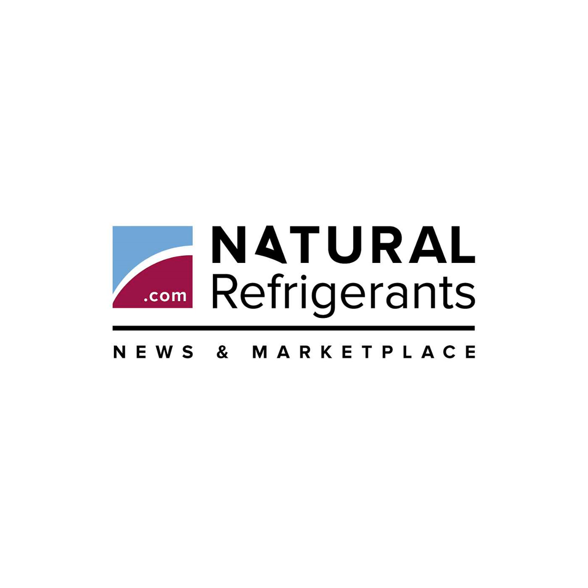It formed a working group on A3 and A2L mildly flammable refrigerants, to consider proposals to enable safe use of R290 and other near-zero emissions next-generation refrigerants. ASHRAE has also started an effort to increase the allowable charge of propane in heat pumps to 4.9 kilograms in outdoor/indirect residential heat pumps and air conditioners. 23 American states have passed legislation that would enable this use of hydrocarbons, in addition to A2Ls.